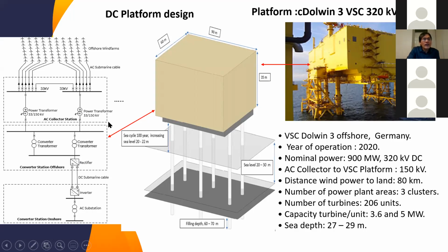What is the DC platform here? Typically, this is the design when we have typically 800 or 900 megawatt. The size of the platform is 60 times 90 meter. All this very big platform is located offshore. When we design, we have to consider a sea cycle of 100 years, where the sea level can increase between 20 to 22 meter. And also the piling here is quite deep because the weight of the platform is very big.